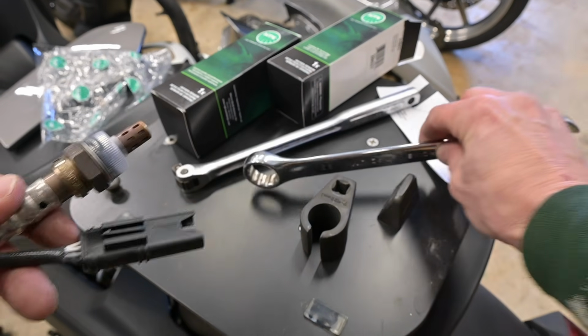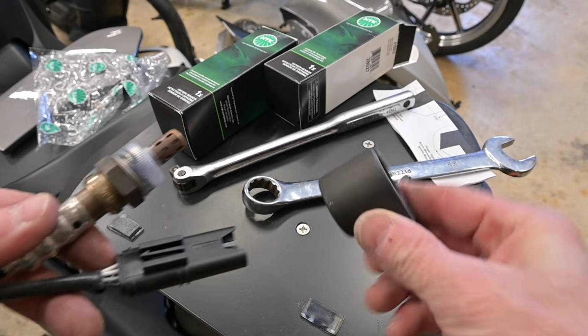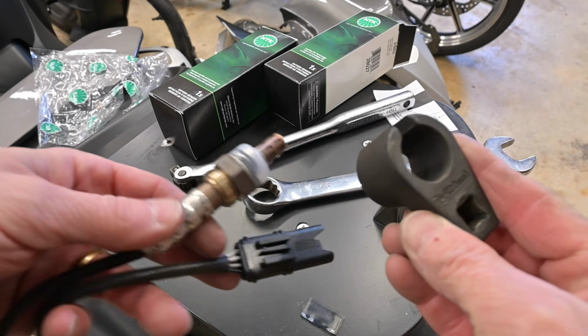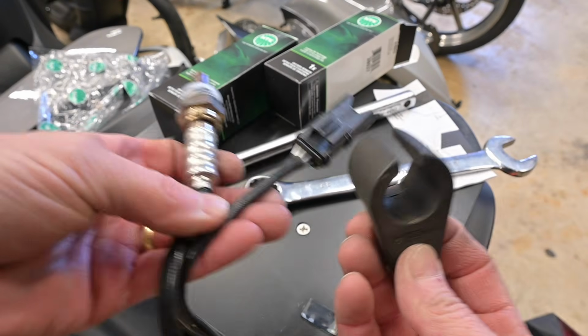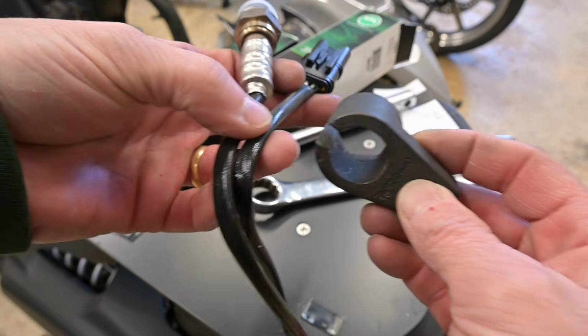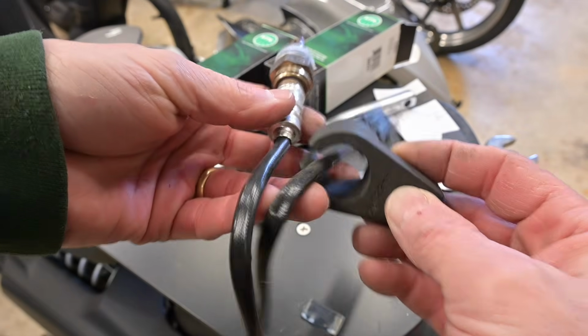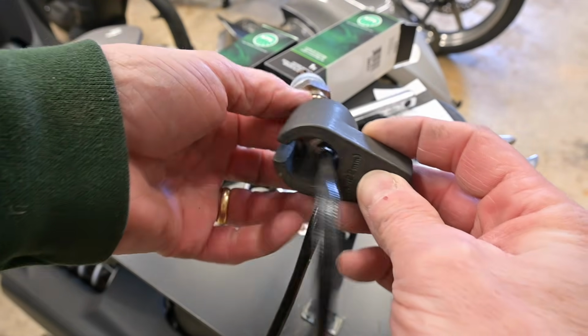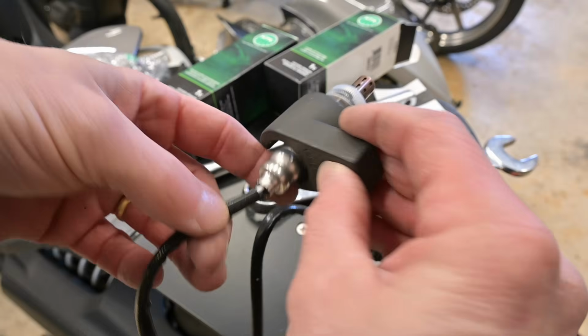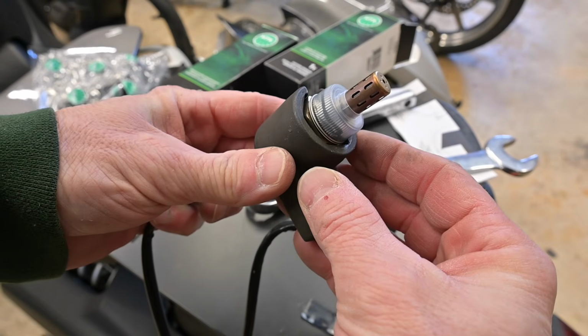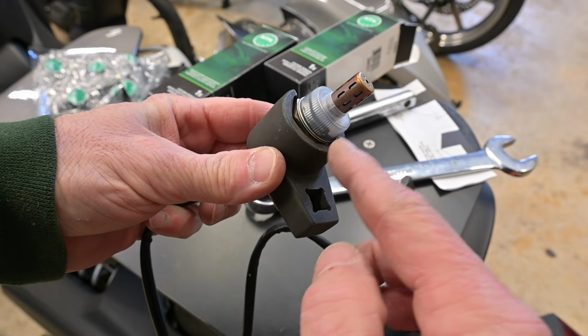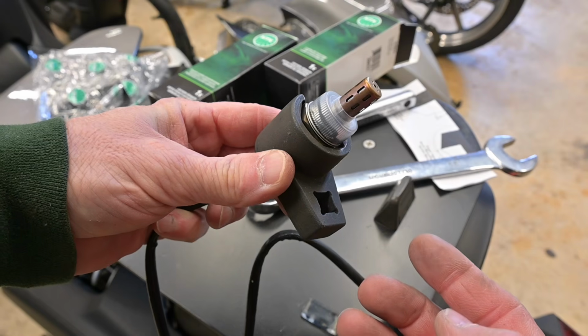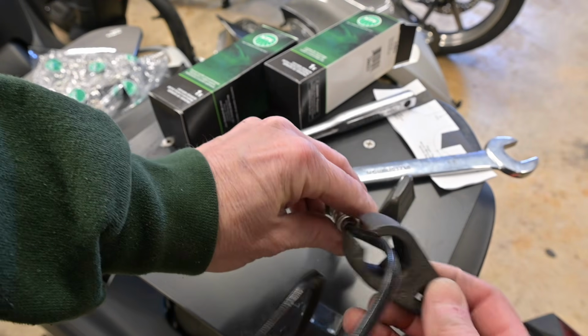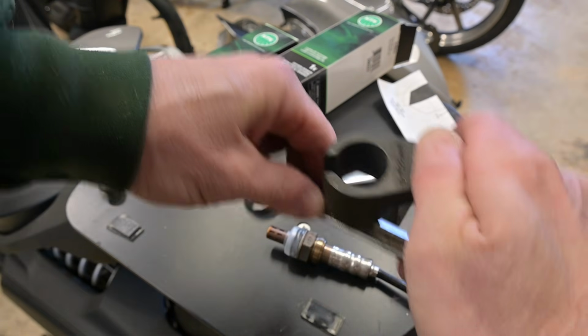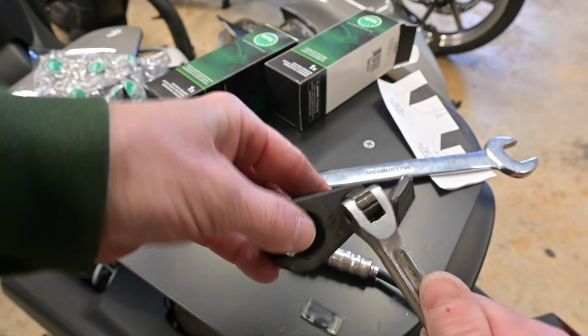The other way of doing this is to use this, which is a specialized tool meant to go over - see, there's a cutout right here. It goes over the wire, so you can do this in place very easily. Slide this over, and again, it'll get a purchase on that hex area right there. That hex is either 22 millimeter or 7/8, either one will work. You would use a breaker bar here that goes on the end like that.